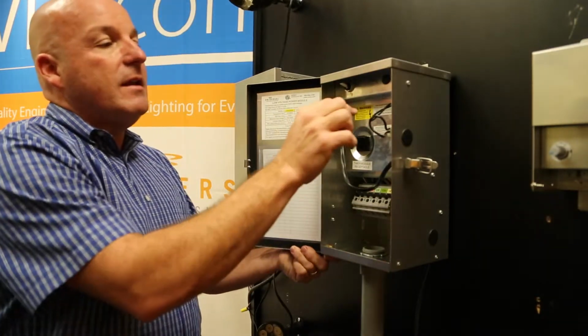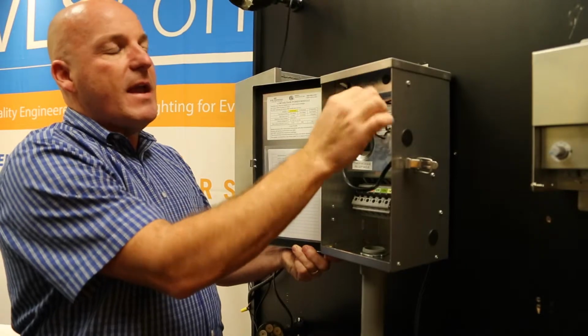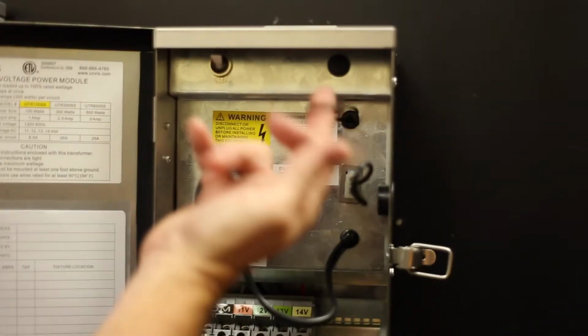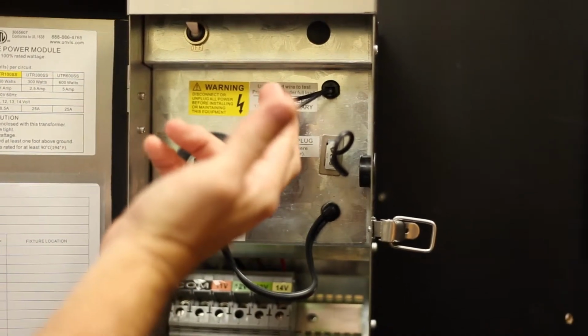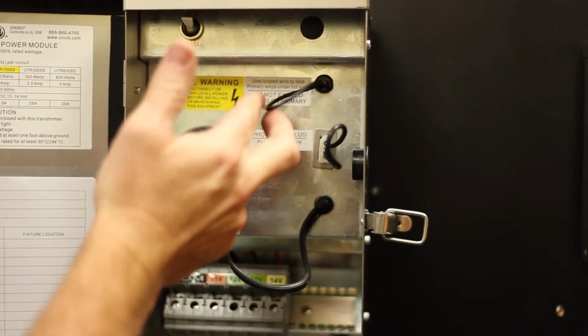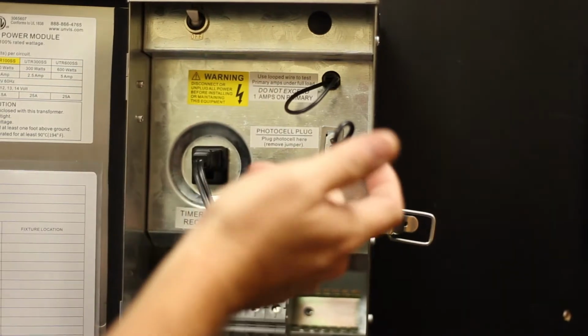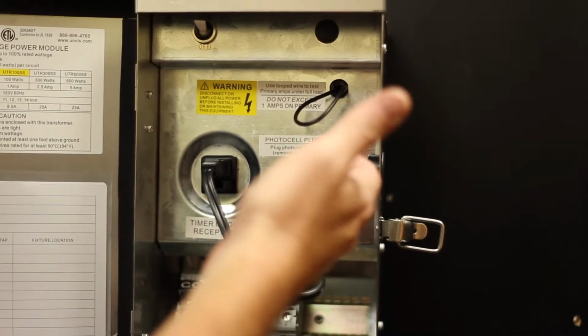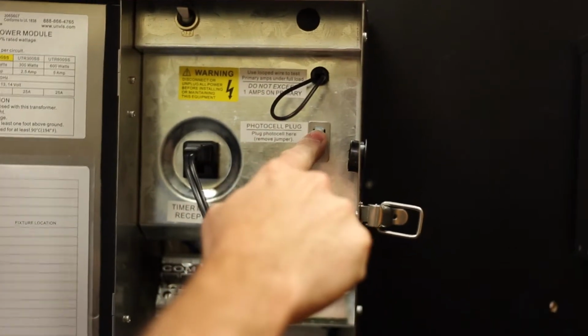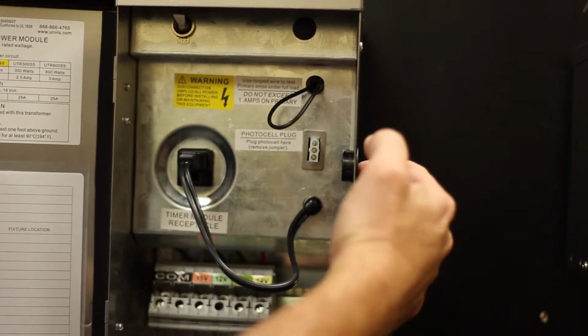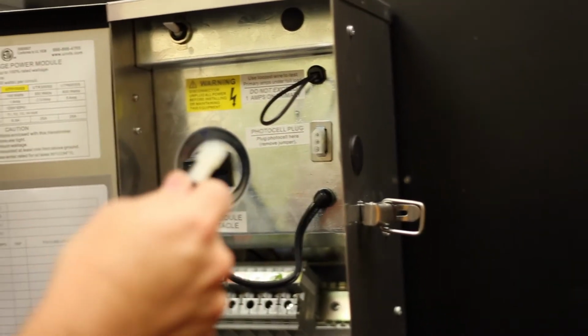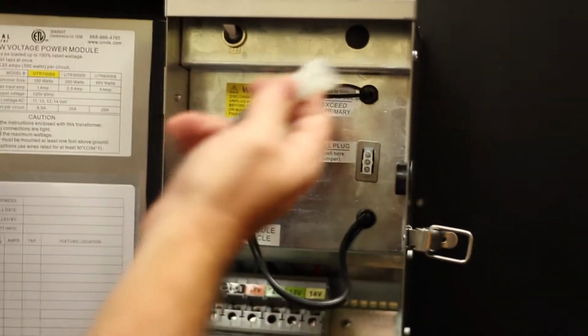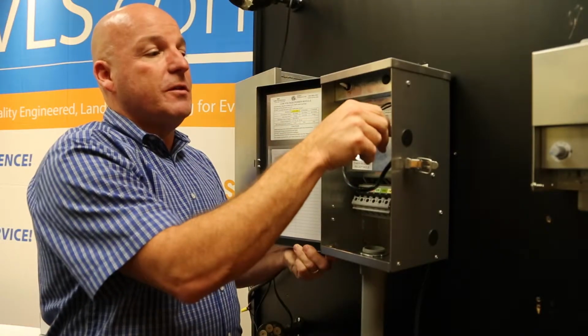We also added a volt-amp loop to each transformer, which measures the primary amp load on every single transformer. This is very important when you're out installing. A lot of people overlook this, or use the photocell adapter to measure it — but if you pull the photocell adapter out and wire a photocell into the side port, you're no longer able to test the total amperage load on the primary side. So we give you that amperage loop to make it easy.